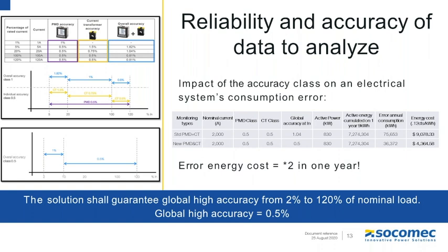On the left side are two tables. In the top table, you can see the accuracy of a basic power monitoring solution, which consists of accuracy of a power meter in purple and the accuracy of the current transformer in yellow. In blue, you can see the global accuracy of the power monitoring device, plus the current transformers that are coming with. Both of them are 0.5, but the result isn't 0.5. The reason is that the global accuracy is not a simple addition. It's a formula that is used to calculate this global accuracy.